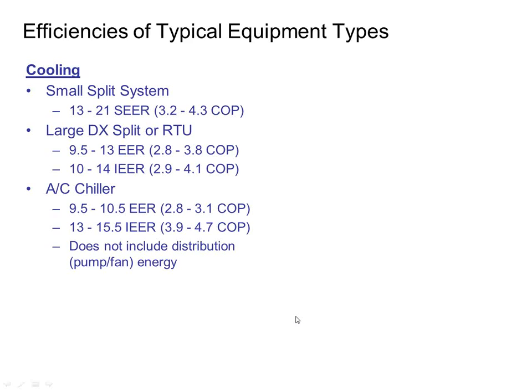One interesting thing that happens on these systems is that each type of product gets its own rating system, which has absolutely nothing to do with any of the other products. So it's basically virtually impossible to use these rating systems to compare a chiller against a rooftop, against a condensing unit, against a boiler, against a VRF system, against a furnace. You cannot compare one to the other directly.